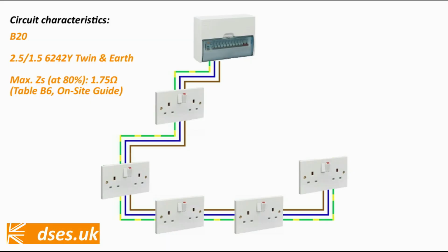Let's use this socket radial as an example. It's a 20 amp circuit wired in 2.5/1.5mm twin and earth, and we've undertaken an electrical inspection where we've identified 5 outlets that it serves. Our aim post-installation is an upgrade of the fuse box to a modern consumer unit with overload, residual current and arc fault protection. We didn't install this circuit, so we don't know the cable run, its history, or if it serves other points of utilisation we haven't seen, perhaps something behind fitted furniture, or maybe it served another outlet in the past that has since been decommissioned. I don't know, this is our first visit to the property.